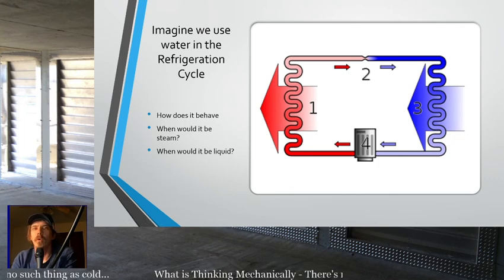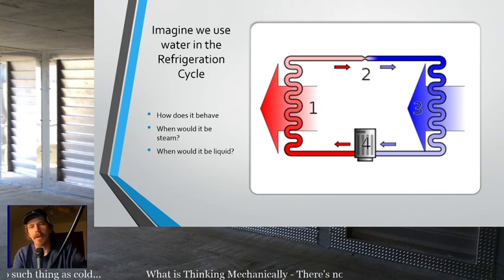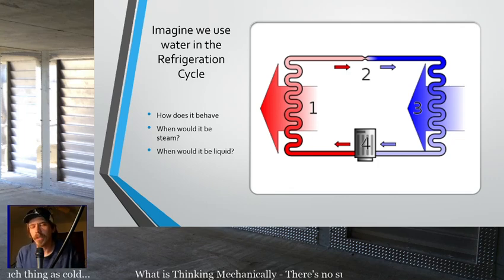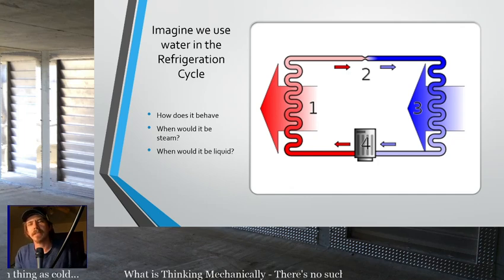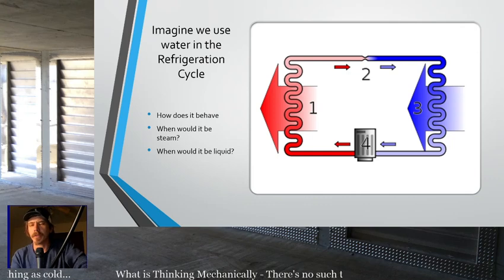Simply to make the water hotter - make the refrigerant, really, but in this case we're pretending it's water. It's going to make that steam hotter so we're able to give off heat to the outside, because the heat has to move from one place to another. We're not cooling anything - we're trying to move the heat from inside to outside. And the only way to do that is to make sure the temperatures are right so that can happen. That's the purpose of the compressor, really.